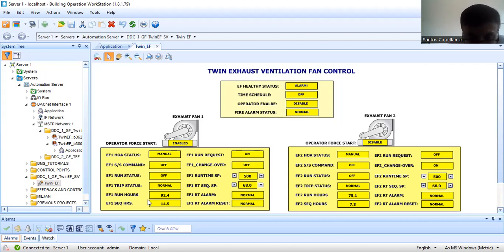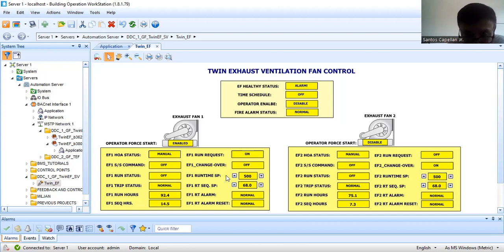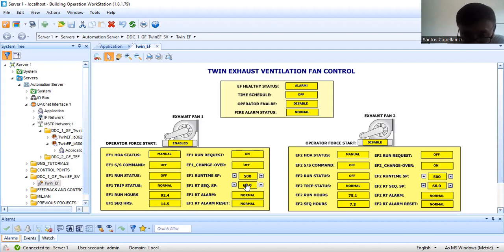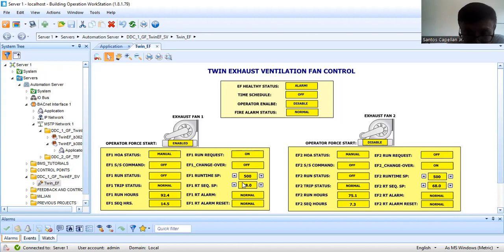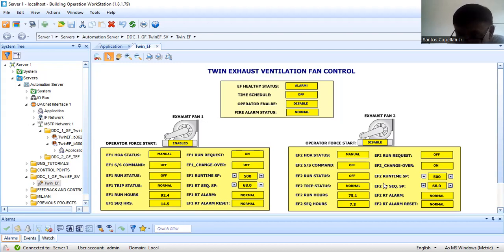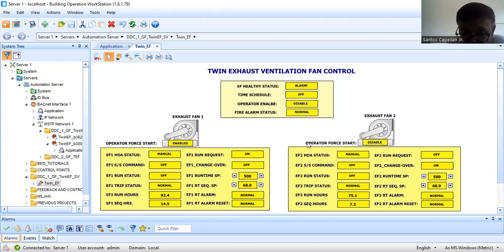Right now, as you can see here, I have the run hours. This is the accumulated run hours for maintenance — for process. The set point for that one is 500. This one is the sequencing hours: 14.5, and the set point is 68. We can set the set point for sequencing to 168 hours — that is one week. So when this fan has been running one week, it will stop, then the standby fan will serve the area. Then if that fan runs 168 hours, it will stop, and EF1 will serve the area. That is sequencing or changeover.